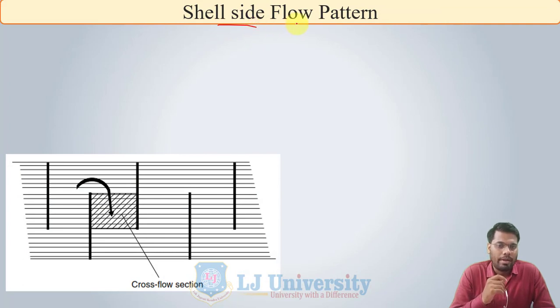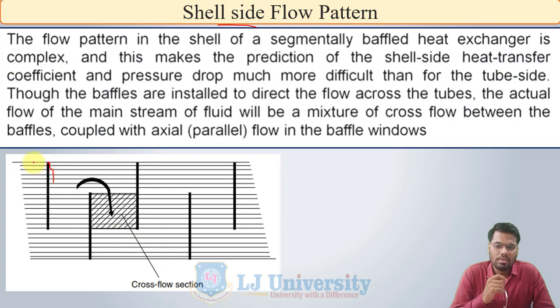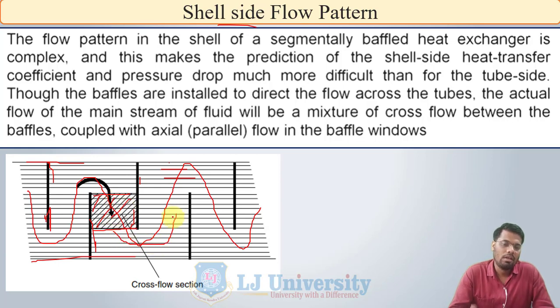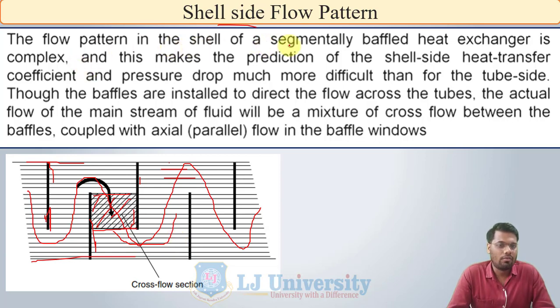This is the shell side flow pattern. In a shell and tube heat exchanger, the shell contains baffles and tubes. When the flow path of the fluid passes between two baffles, at the tip of the baffle, the flow is cross flow — the fluid flows over the surface of the tube in a cross flow pattern. When fluid is passing through the baffle window area, the flow is counter or parallel to the fluid flowing inside the tubes. The flow pattern in the shell of a segmentally baffled heat exchanger is complex, making prediction of the shell side heat transfer coefficient and pressure drop much more difficult than for the tube side.